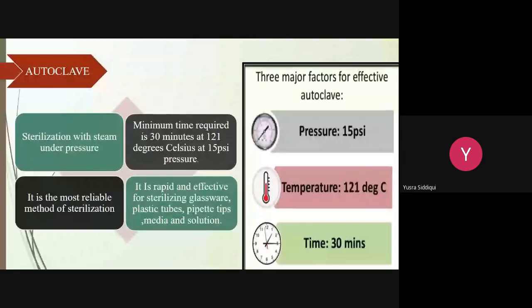We can say the autoclave is a container similar to a pressure cooker. It is filled with the objects to be sterilized and then sealed. Next, high temperature steam is forced in under high pressure, thereby displacing air. Moist heat destroys microorganisms by irreversible coagulation and denaturation of their enzymes and protein structures. The time and temperature needed depend on the pressure and the type of microorganism to be inactivated. After the necessary time has passed, the steam is released and the sterilized objects are removed. The entire cycle can take from 15 to 60 minutes.